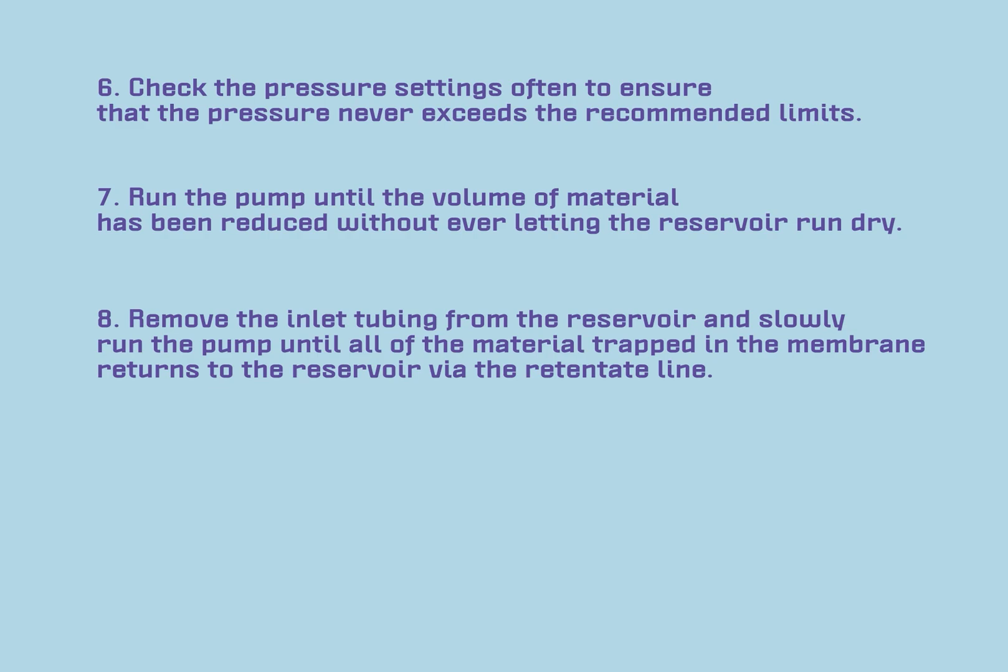Remove the inlet tubing from the reservoir and slowly run the pump until all of the material trapped in the membrane returns to the reservoir via the retentate line.